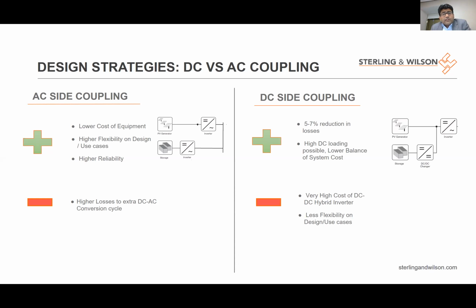Now let's come to the DC side. There is a DC side coupling which is possible, which essentially means that instead of converting solar power into AC, you use a DC to DC converter and straight away charge your batteries. On the face of it, it looks to be an obvious solution, and everybody thinks this is the way it should be. It will help increase the DC loading of the system, which means the balance of system cost comes down, but things are not that simple.